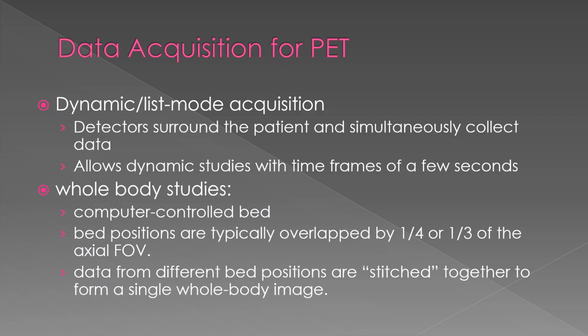And then the whole body studies, this is a computer controlled bed. These are the bed positions that I told you about when we're scanning whole body PET studies. So the only time that we are not doing whole body PET is if we're doing the brain or the cardiac studies. But anytime you're doing oncology studies where you're doing the body, then you're doing a whole body study and it'll have multiple bed positions.